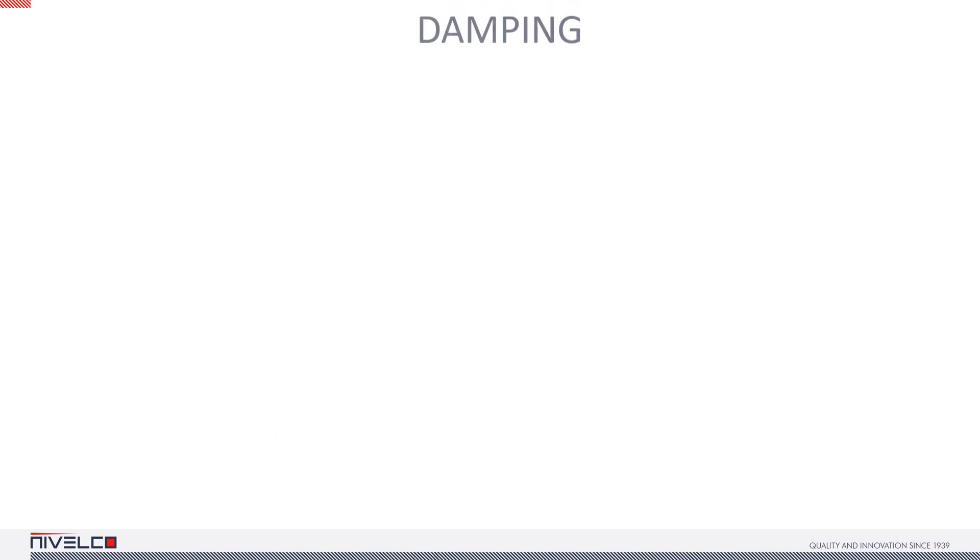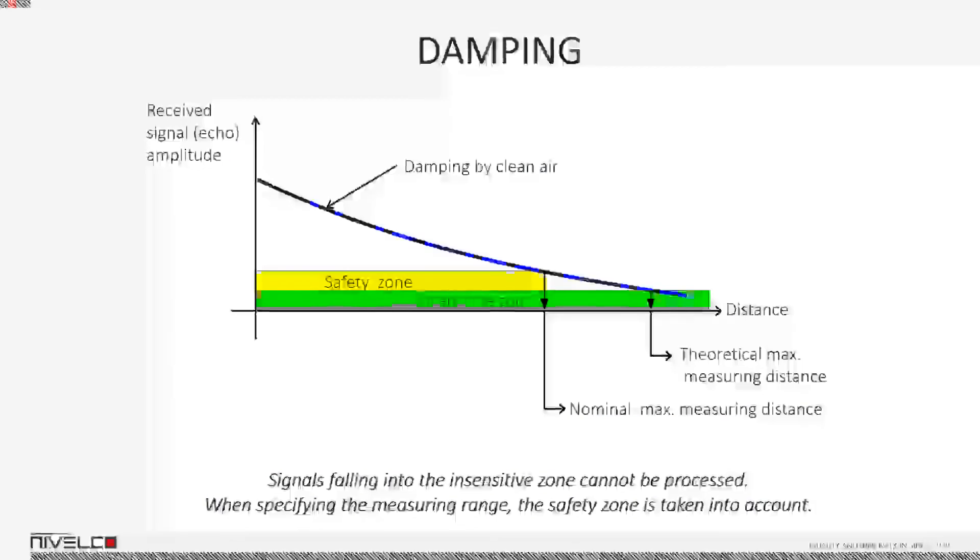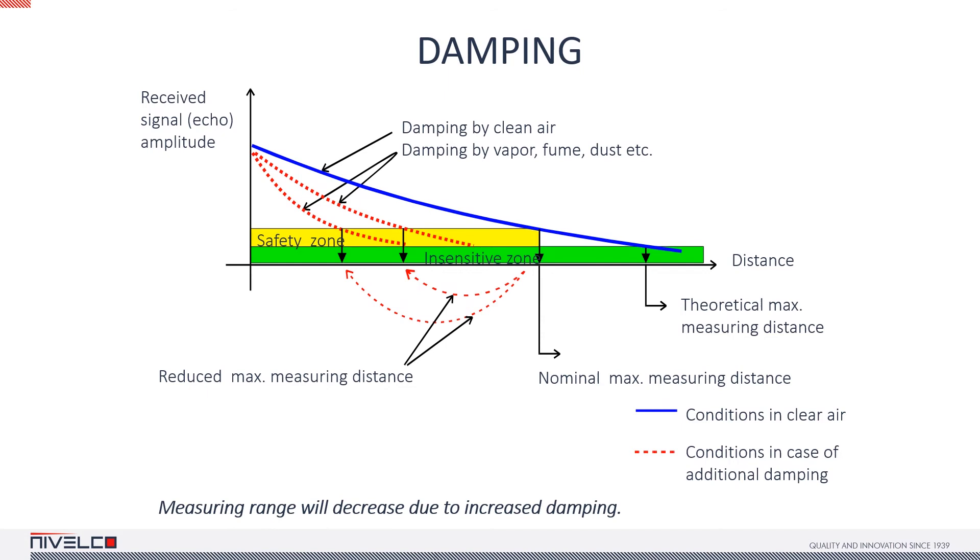The blue curve in this diagram illustrates the signal dampened by clean air, and the green line is the insensitive zone where the echo is so weak that the device is unable to catch it. The theoretical maximum measuring distance of a device is where the echo level first hits the insensitive zone. The safety zone is in which the device can measure reliably and whose maximum we call the nominal measuring range. Additional damping factors may reduce the device's maximum measuring range. Therefore, it is vital to know the physical properties of the measuring medium and the environment before purchasing a system.